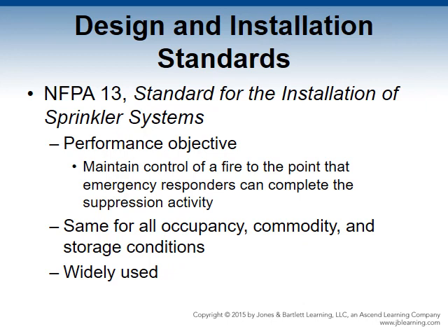NFPA 13, standard for the installation of sprinkler systems. The performance objective from the first edition, created in 1896, to the most current edition is to maintain control of fire to the point that emergency responders can complete the suppression activities. Controlling the fire necessitates containing the fire to a general area of origin.